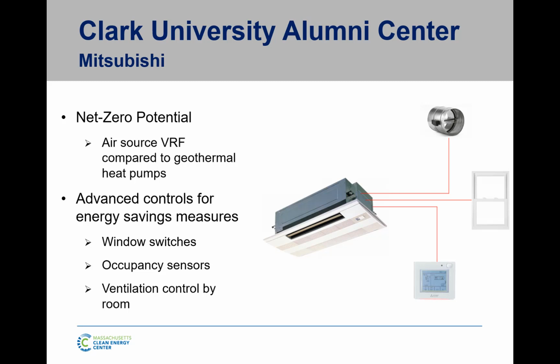Some of the ways we accomplished that, beyond the efficiency of just the VRF system itself, was using some advanced controls that can really come built in with these systems for energy saving measures. First being a ventilation damper that's tied directly to the fan coil unit. So the unit's running and on because the room is occupied, that damper opens and allows ventilation air directly to the unit. Someone leaves the room and the room's unoccupied, close the damper so we're not bringing in ventilation air. Why ventilate a room that doesn't need to be?